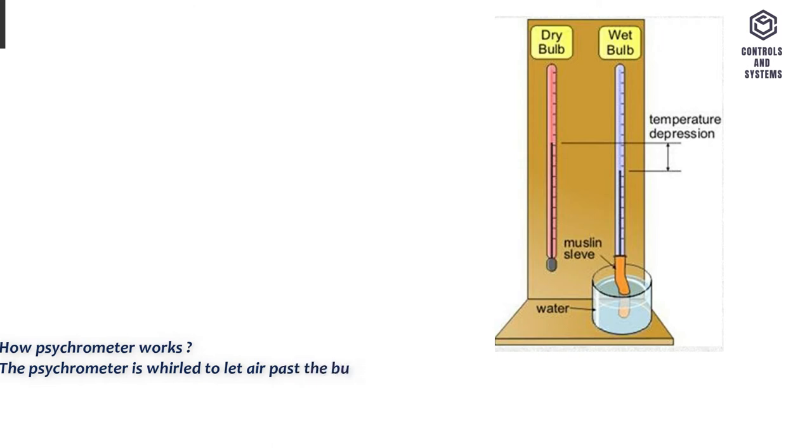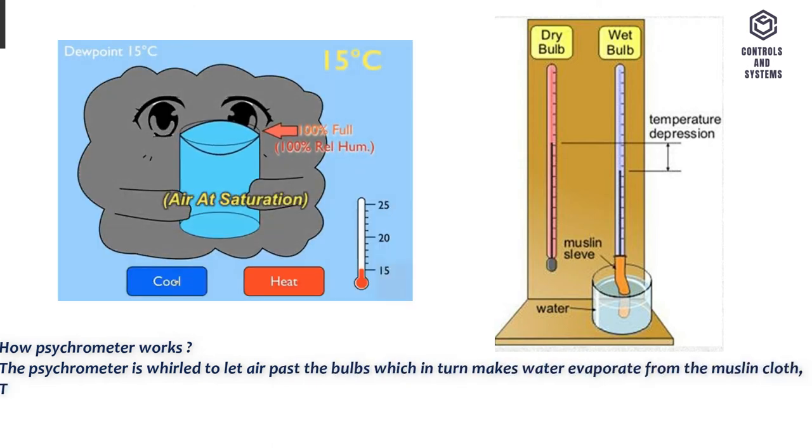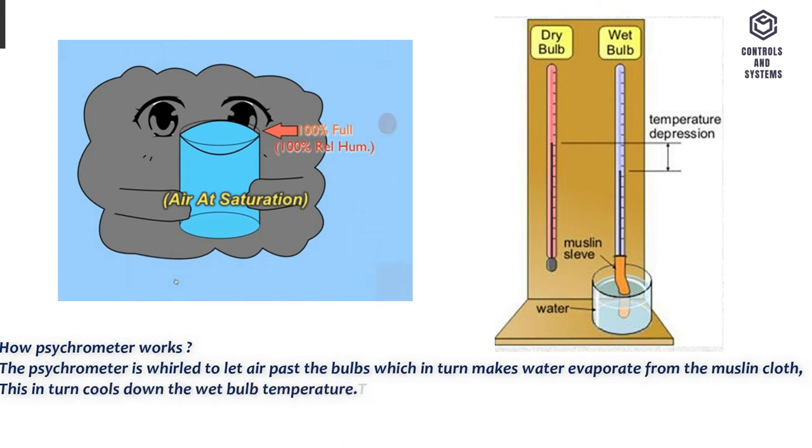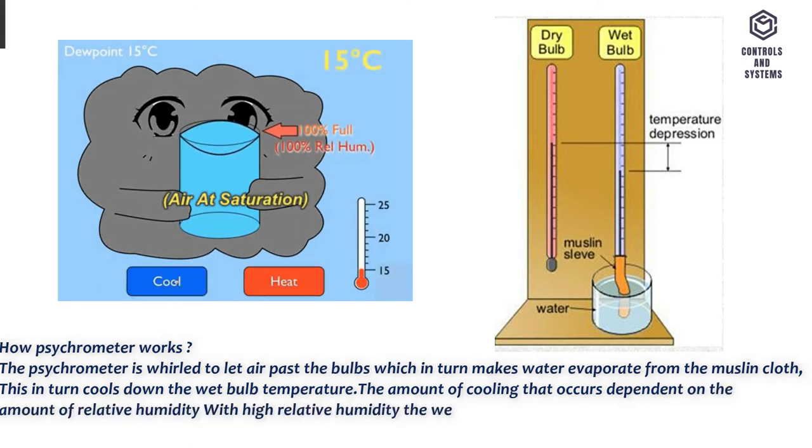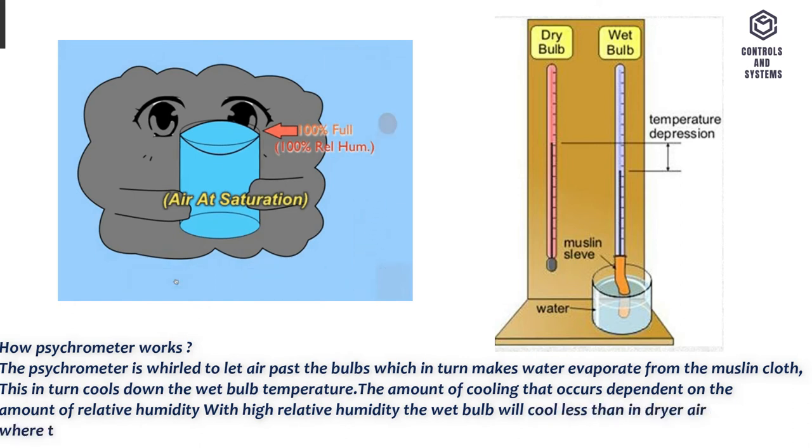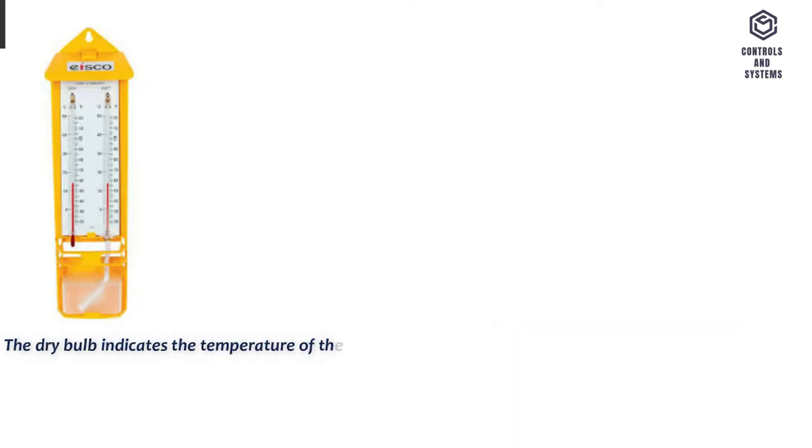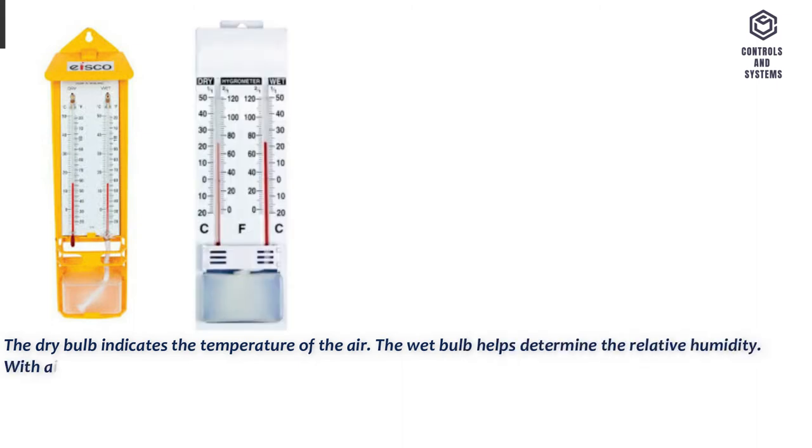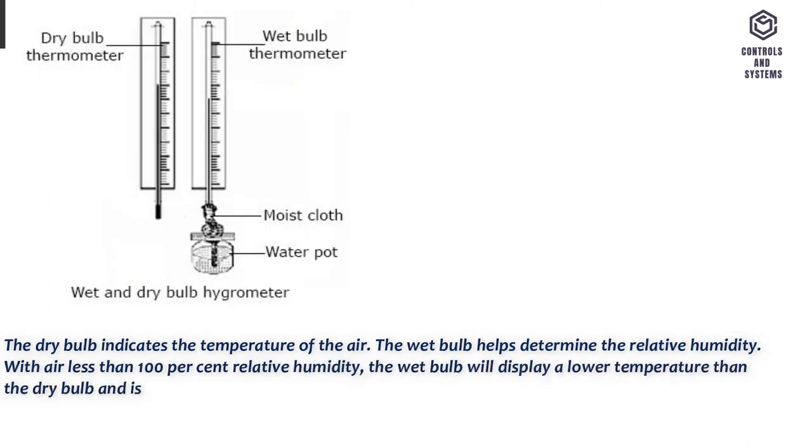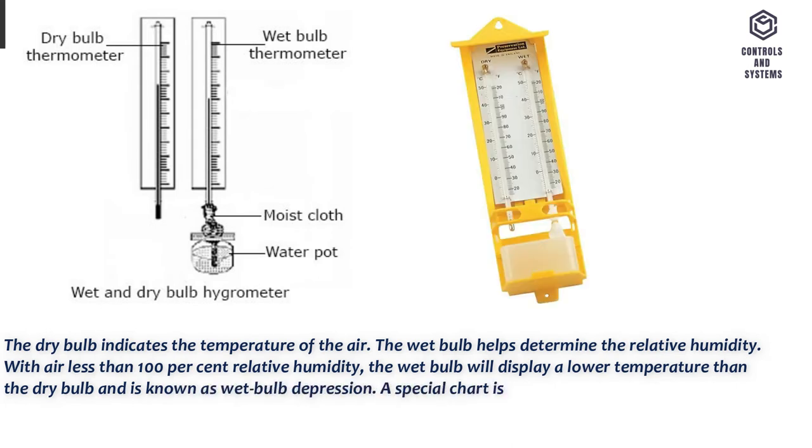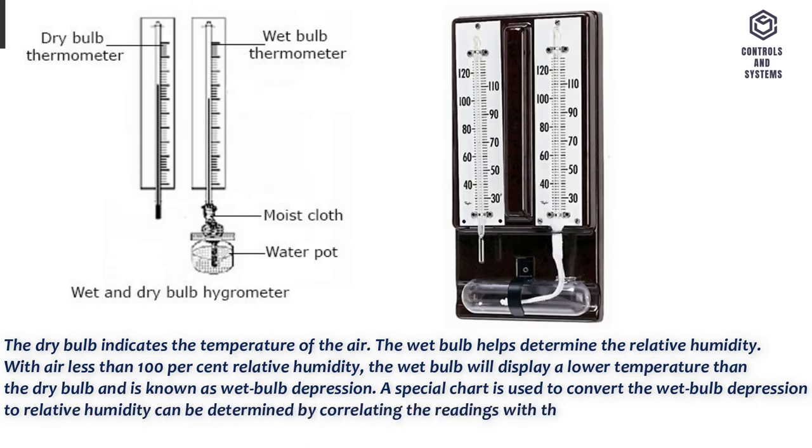How psychrometer works. The psychrometer is whirled to let air pass the bulbs which in turn makes water evaporate from the muslin cloth, this in turn cools down the wet bulb temperature. The amount of cooling that occurs depends on the amount of relative humidity. With high relative humidity the wet bulb will cool less than in drier air where the water in the muslin will evaporate faster. The dry bulb indicates the temperature of the air. The wet bulb helps determine the relative humidity. With air less than 100% relative humidity, the wet bulb will display a lower temperature than the dry bulb and is known as wet bulb depression. A special chart is used to convert the wet bulb depression to relative humidity, which can be determined by correlating the readings with those on a simple slide rule, which is supplied with each instrument.